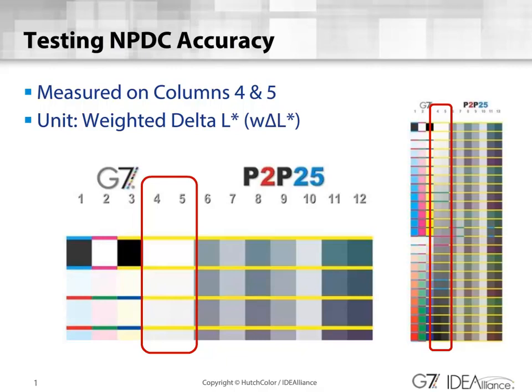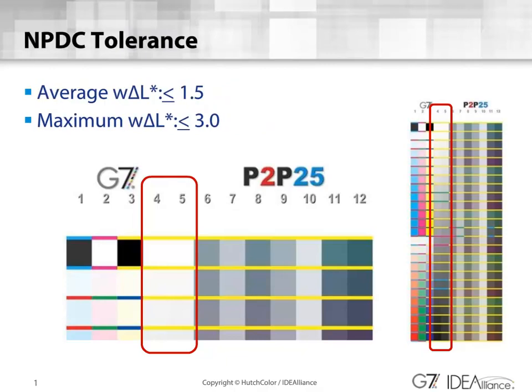In other words, the difference in L star from what was printed compared to what was asked for. The weighting function I'll talk about in a minute. The central 23 patches of each of these two scales, not the first patch or the last one, that's 0 and 100, but all the other patches, the average weighted delta L star must be 1.5 or less. The maximum weighted delta L star must be 3.0 or less. And preferably you want to see numbers around about half that level.